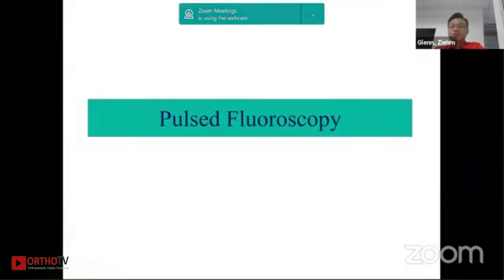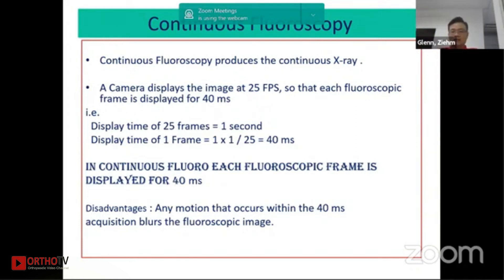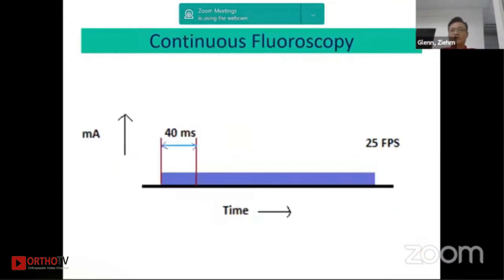Conventionally, fluoroscopy is in the continuous mode. The camera display is usually 25 frames per second, so each fluoroscopy frame is displayed for 40 milliseconds. In one second there are 25 frames, so the display time for one frame is 40 milliseconds. The disadvantage of continuous fluoroscopy is that any movement will cause the image to get blurred.